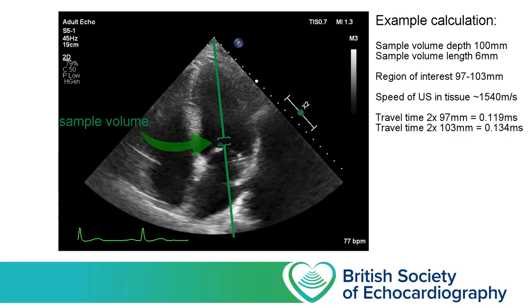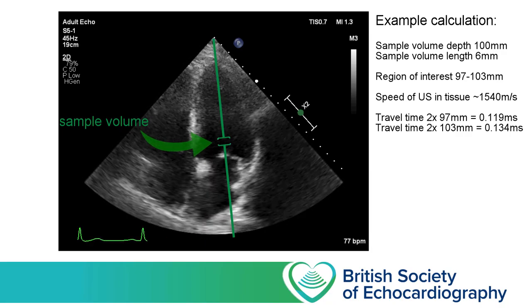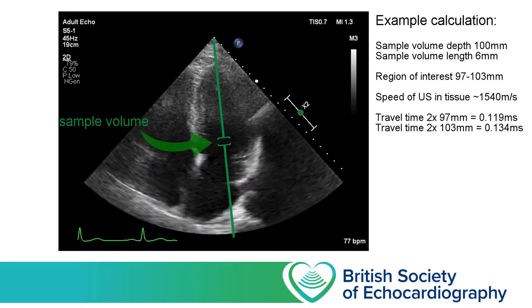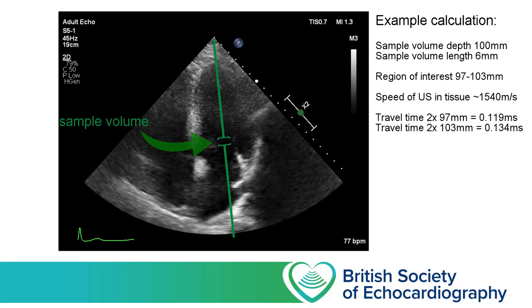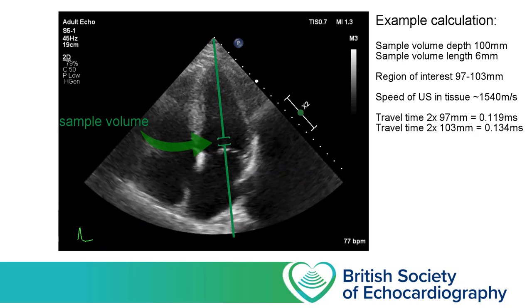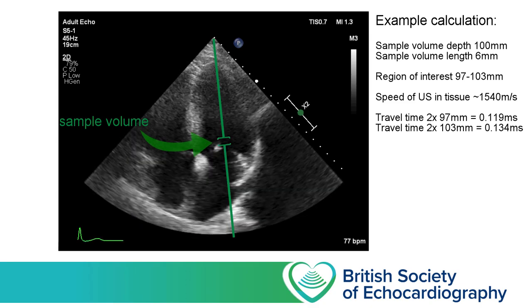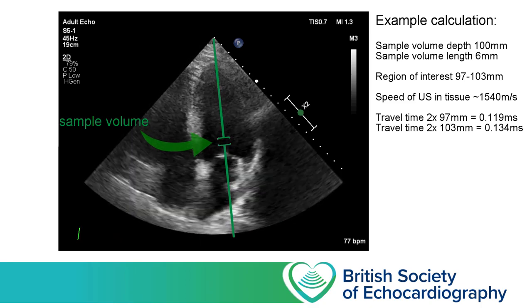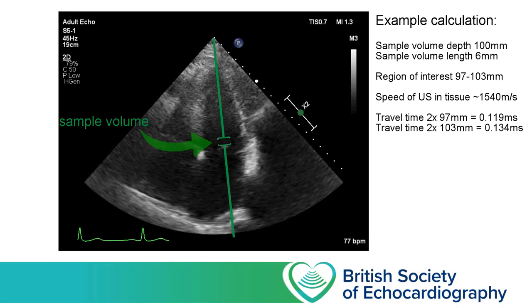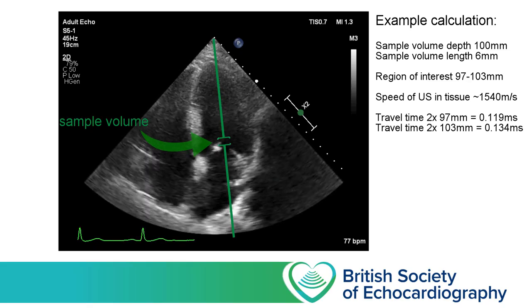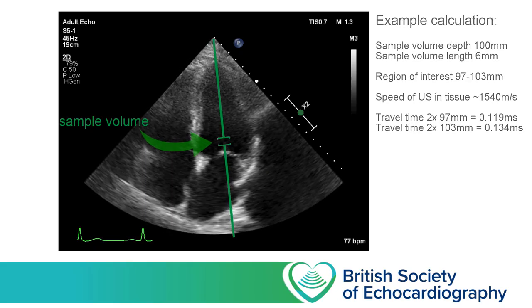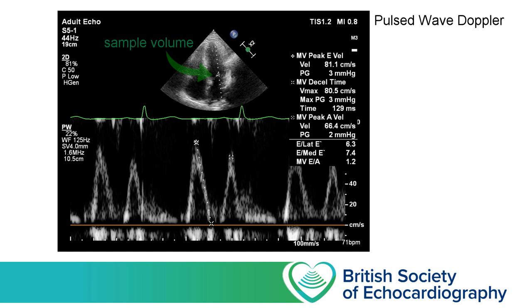The ultrasound software knows that if it sends out a pulse of ultrasound and it returns before 119 microseconds, then it won't have had time to reach the sample volume and return. Likewise, any signal returning later than 134 microseconds would have been reflected from a structure deeper than the sample volume. It knows to ignore all information returning outside of that gate, and only use information that arrives between 119 and 134 microseconds after the pulse was emitted. By sending several thousand pulses along this single scan line each second, the software is able to measure the shift in phase between transmitted and received waves, and then use the Doppler equation to calculate velocity.